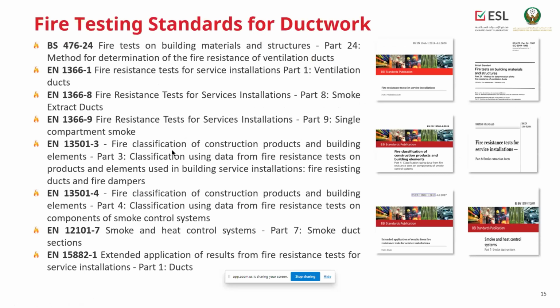Fire testing standards for ductwork: actually, these are testing and classification and product standards also. For today's session, we are focusing on BS. So we have BS 476-24, and for EN, we have 1366 part 1, 1366 part 8, and part 9. I believe Daniel already explained in detail. Basically BS 476-24 includes all three types of product that we explained: ventilation, kitchen extract, and also the smoke control duct. It comes under one standard.